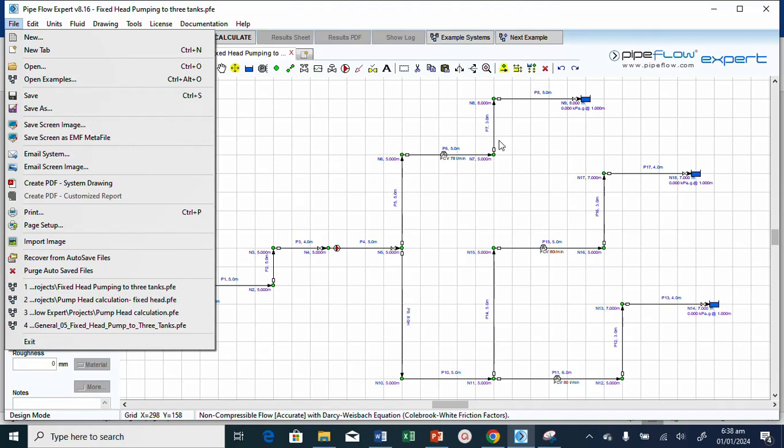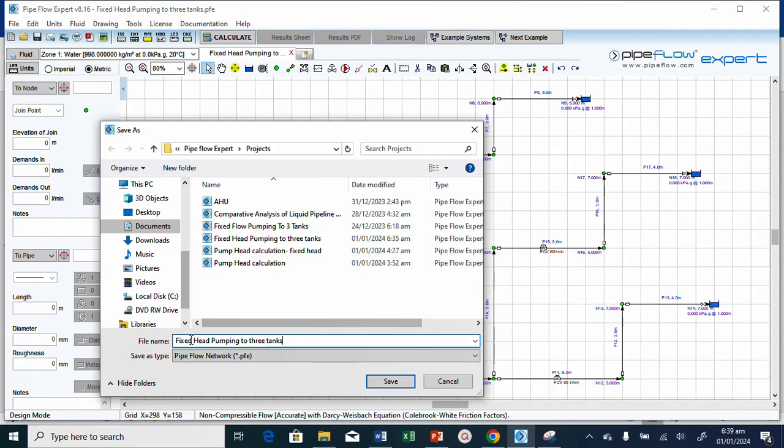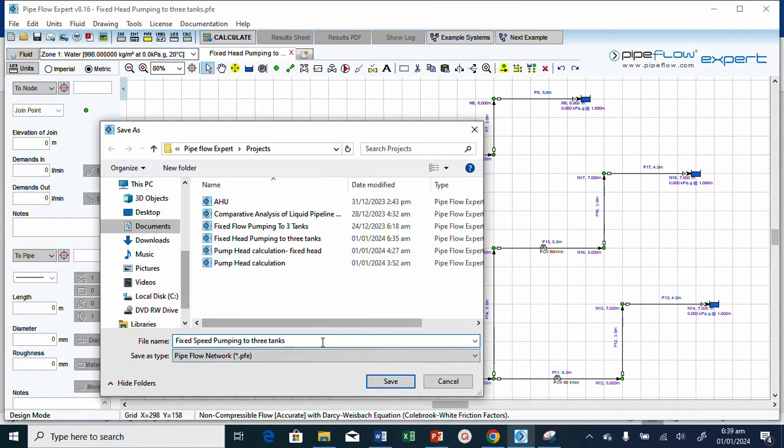What I want to explain here is how to select the pump based on the fact that you've used a fixed head. Now you know the flow rates. What you need to do is look at your pump performance curve and make selection. Before we do that, I'll save this. I need to change this from fixed head pump to three tanks to fixed speed pump into three tanks.